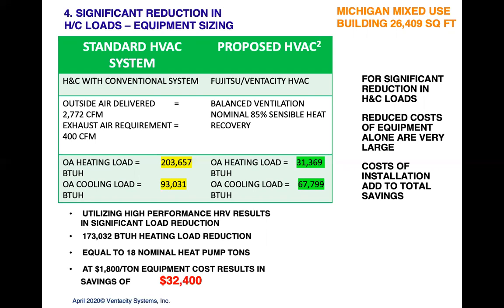By using very high efficiency heat recovery for your outside air, we reduced the load from 203,000 on heating down to 31,000. What you'll see there is the dominant load became the cooling load at just under 68,000 BTUs an hour. But the total load on the building for the equipment required, we were able to reduce the system by 18 nominal tons as far as the heat pump system goes. At $1,800 a ton, just the equipment cost was $32,000 in savings.